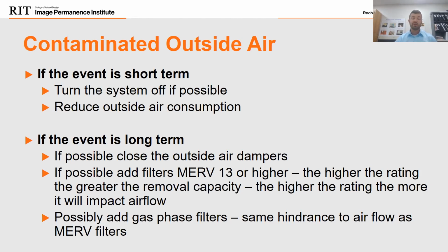We have worked with some institutions that have worked with their local government agencies to come up with a plan to close the dampers when major fires happen, because that's all they can do. Or maybe they can install some of the gas phase filters, as we talked about earlier, for removing that smoke, or even a MERV 13 filter if your systems are capable of handling those.